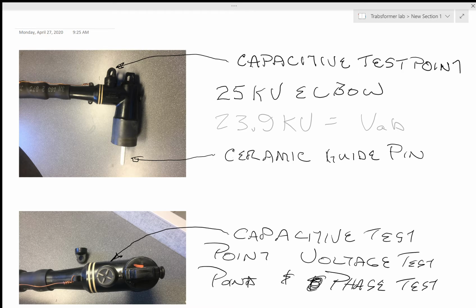Anyway, these are our 25 kV elbows. This is a heat shrink right here. You put it on with a heat gun. You've got to prep the wire, so many inches for this, so many millimeters for this, and so on. You have a ceramic guide pin, and then I'm going to show you in a minute another pin that's out of the elbow, and it fits into a lug on the end of the wire.